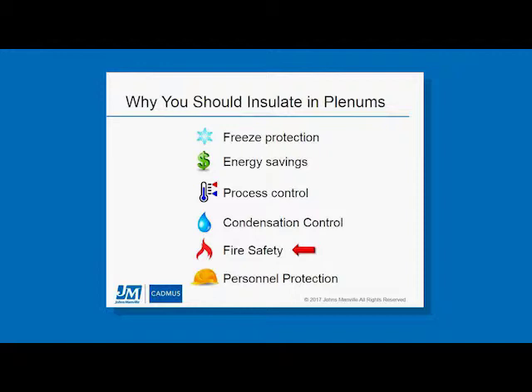So insulating those systems to minimize the potential for condensation is definitely something that is done throughout the U.S. Fire safety: if you're putting materials into a plenum space, you don't want them to become fuel for the fire in the event of a fire. And lastly, if you have people working in a plenum space around steam piping and hot ducts, you want to make sure that they're protected so that they don't get burned. So again, that is another reason for insulating those mechanical systems in a plenum space.